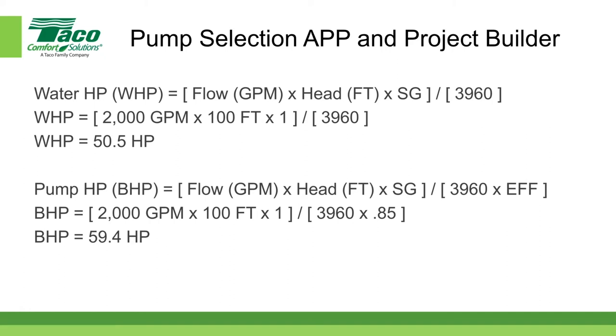The difference between water horsepower and brake horsepower is that we now include efficiency. The formula is the same, but you divide not only by 3960 but also by the efficiency. With 85% efficiency assigned, 2,000 times 100 times 1 divided by 3960 divided by 0.85 comes out to 59.4 horsepower. So the theoretical water horsepower is 50.5 and the actual brake horsepower is 59.4. The difference between those two is the efficiency.